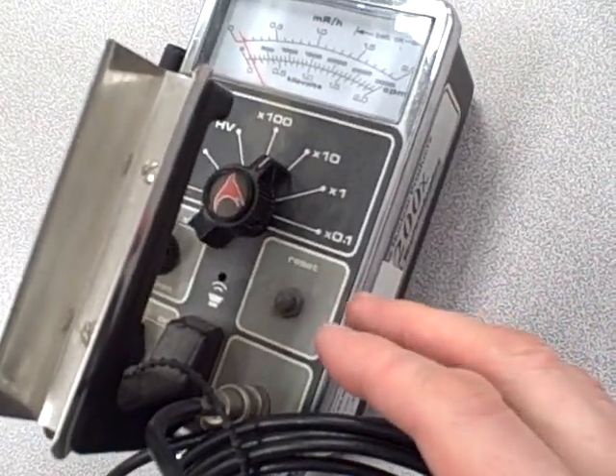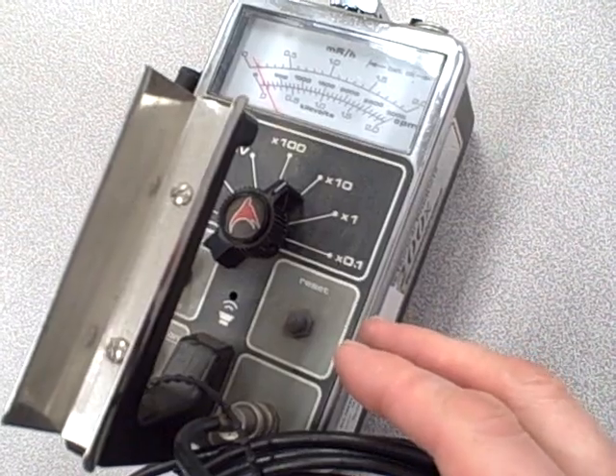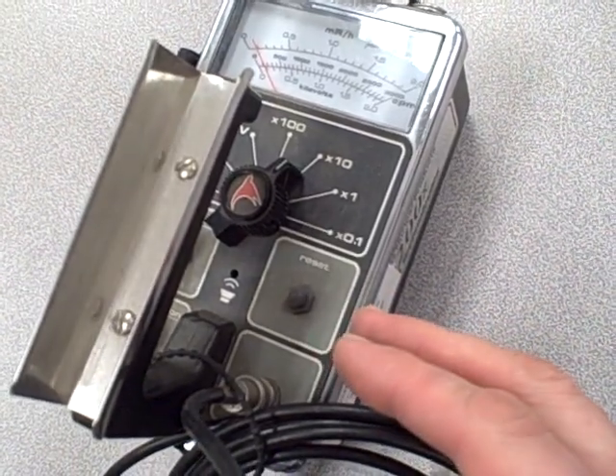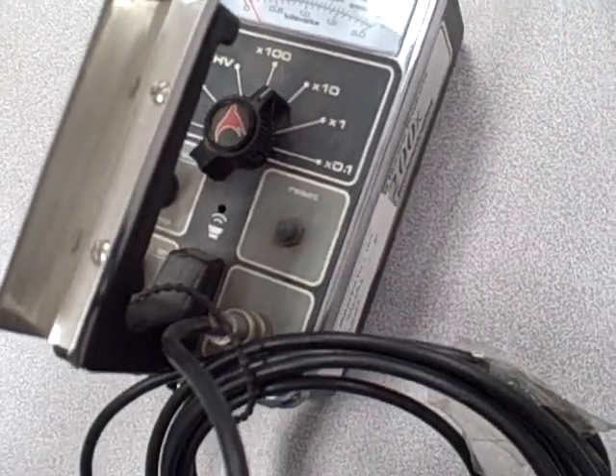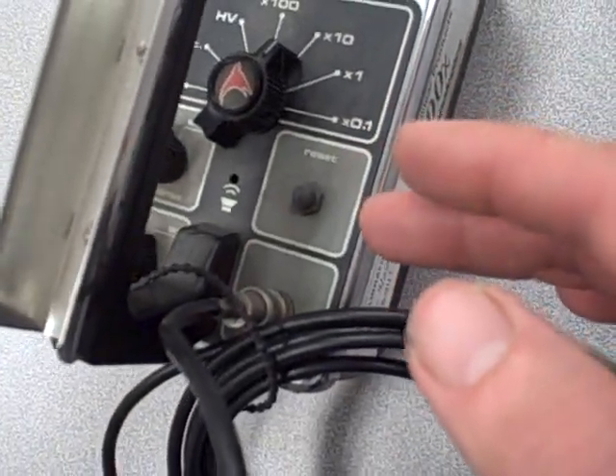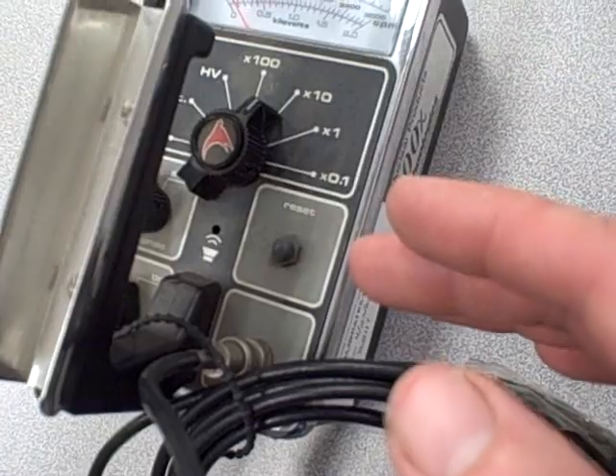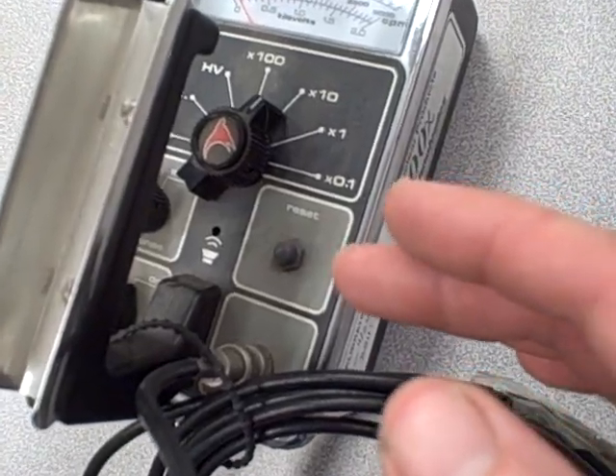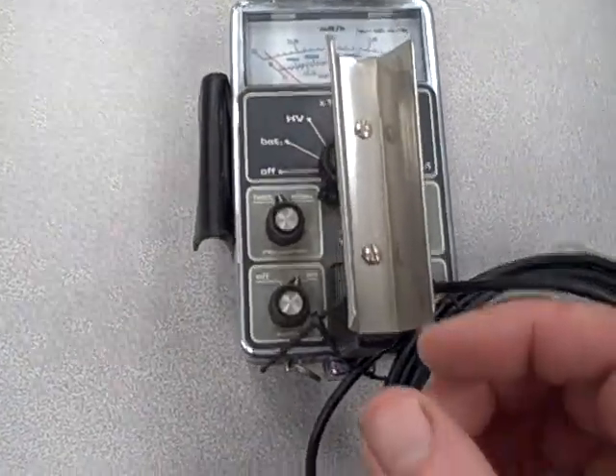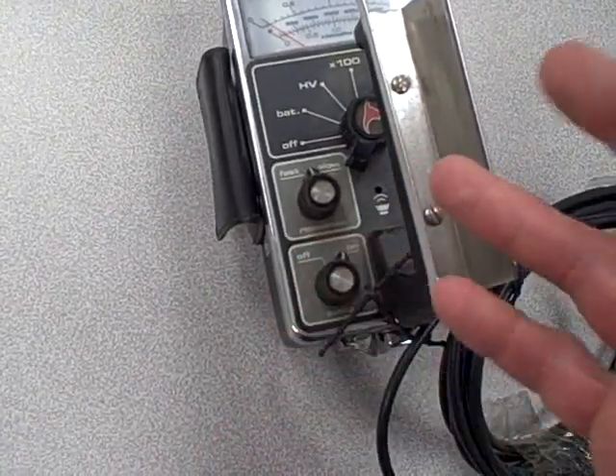I don't know what the actual division ratio is on this particular Geiger counter, but they do that because the actual number of radiation particles flying through the tube is a lot more numerous than what would be typically audible. So if you had one click for every particle, you'd just hear a buzz. So what they do is they divide that number of clicks, like maybe one click for every 1,000 particles or something like that.